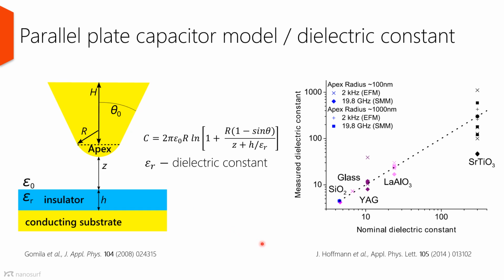Then if you know the thickness of the film and you have measured the capacitance in a calibrated way, you can extract the dielectric constant. Knowing the thickness of this dielectric film is very important in this measurement. Without this information, it is impossible to draw any quantitative conclusions if you're using this model. But you can also work with bulk samples, and then the extraction of the dielectric constant requires calibration standards. And if you have these standards, your measurement is more precise than the one that is made with electrostatic force microscopy. This you can see on this figure on the right.